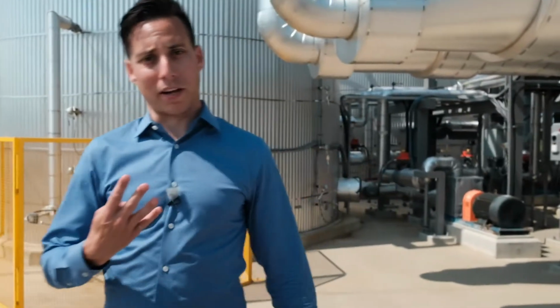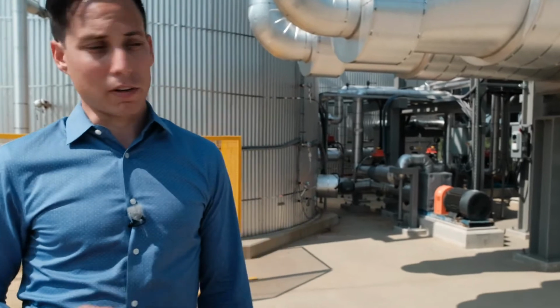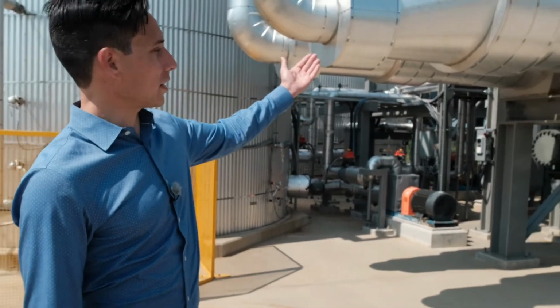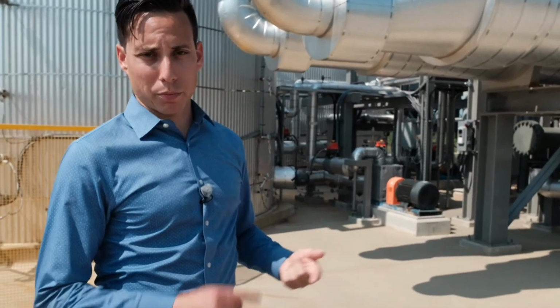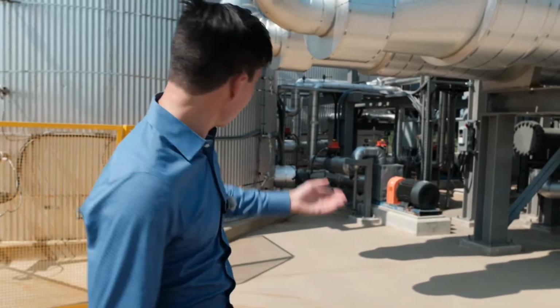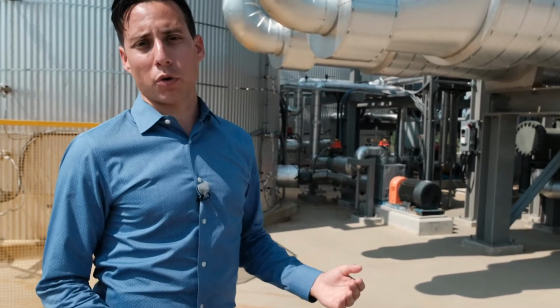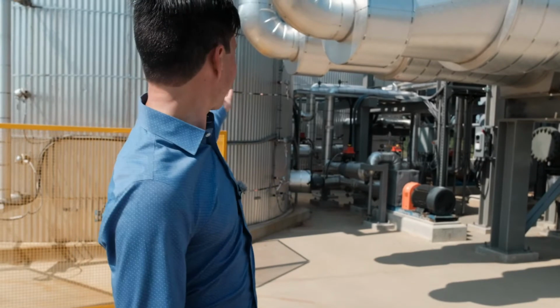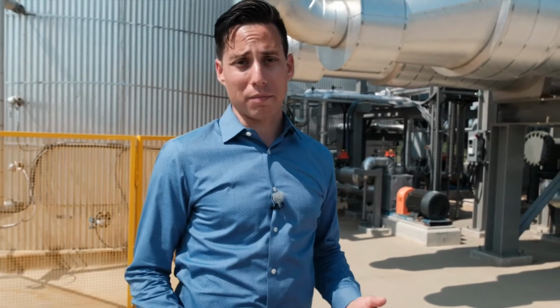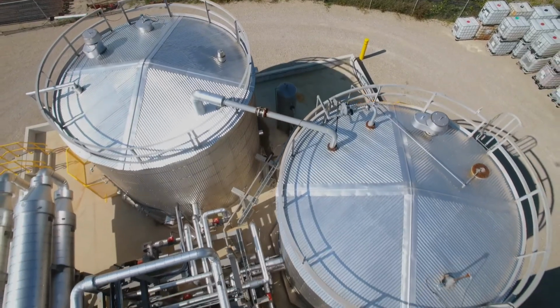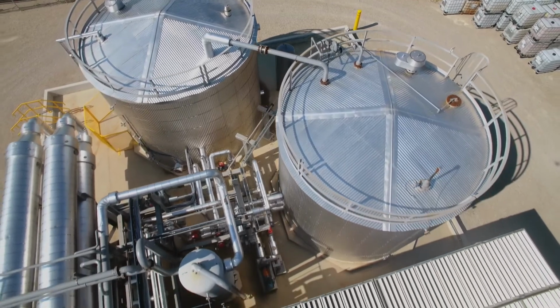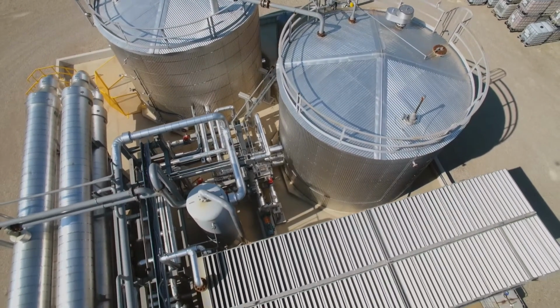It consists of 4 main components: a thermal fluid, in this case a mineral oil, heat exchangers, which enable the heat transfer between the oil and the air, a cold storage tank, which stores the fluid while it's cold, and an insulated hot tank, which stores the fluid while it's hot. This thermal storage system is one of the key innovations developed by HydroStor. It enables the process to be adiabatic.